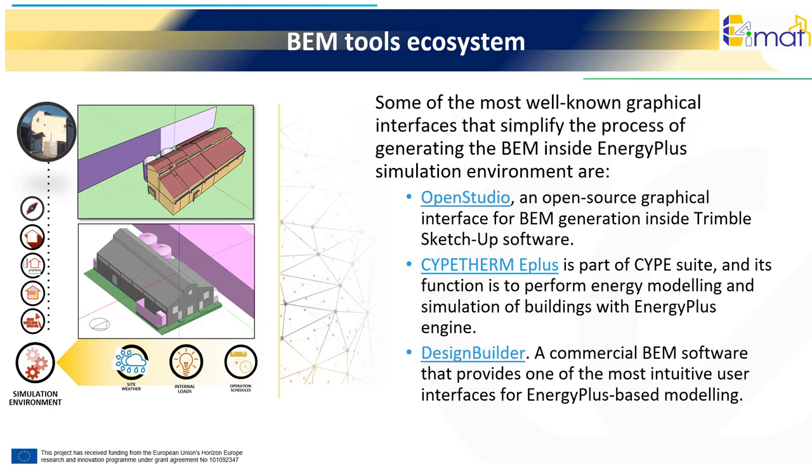There are multiple programs and tools that shape the software ecosystem around the EnergyPlus simulation environment. Regarding the generation of the model's geometry, its location, orientation, as well as its architecture, materials, and different active systems, these parameters can be introduced directly into EnergyPlus, which is a highly time-consuming process, or by either the importation of a gbXML file provided by a BEM model, or by the use of different graphical interfaces.